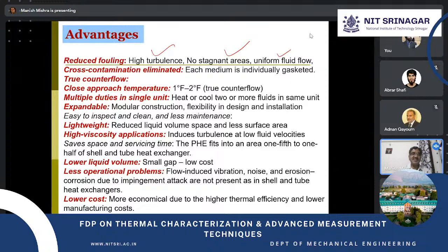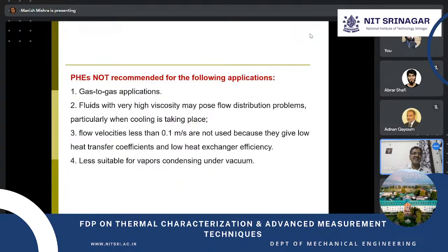But the issue is it cannot be recommended for gas to gas applications because the passages available are too small, so it cannot accommodate the high specific volume. Similarly, for very high viscosity fluid this cannot be recommended. Wherever flow velocity is less than 0.1 meter per second, again this is not suitable, and like gases, even for steam it is not suitable.